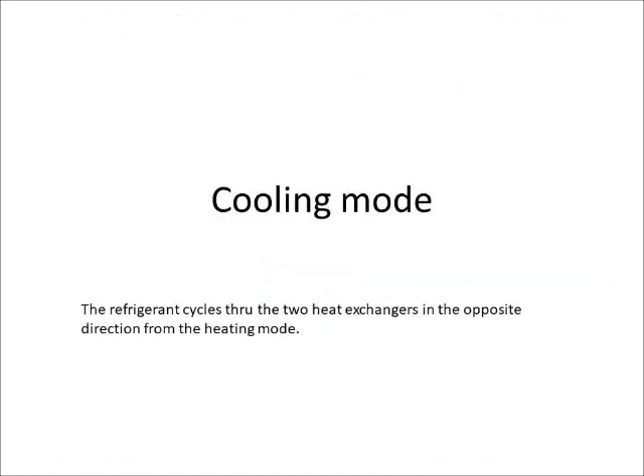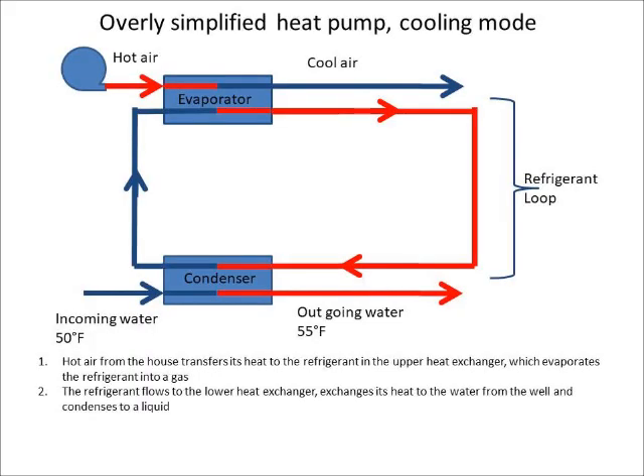Cooling mode. Next, we'll see how the refrigerant cycles through the two heat exchangers in the opposite direction from the heating mode. In this simplified drawing for the cooling mode, we'll see that the hot air from the house transfers its heat to the refrigerant in the upper heat exchanger, which evaporates the refrigerant into a gas. The refrigerant then flows to the lower heat exchanger, exchanges its heat to the water from the well, and condenses to a liquid. Notice that the well water is heated from the house air.